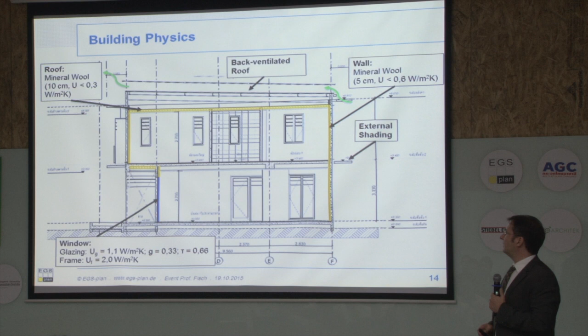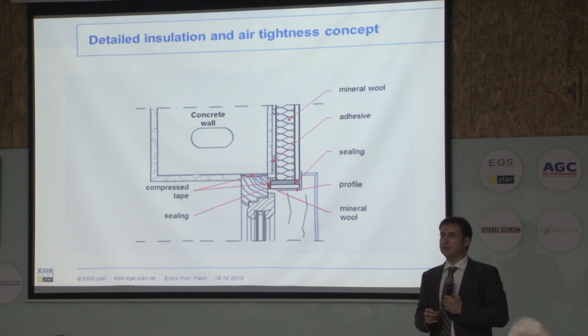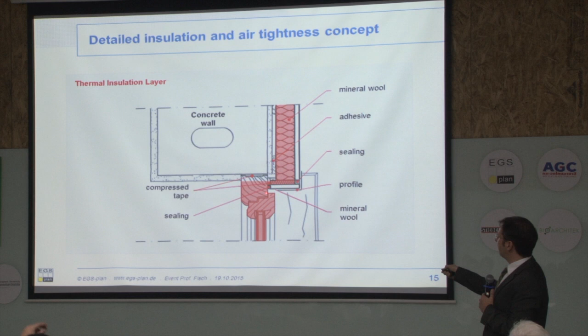We have external shading, not only in the area of the window, but the shading also protects the wall to reduce the solar heat gains through the wall. Also the roof is back ventilated, which also reduces the cooling load in the building. So we are not only designing the rough overall building envelope, we also really go into detail, because in most projects where people are applying thermal insulation, they probably put the insulation until here, and then you have a gap between the window frame and the thermal insulation, and through this gap you are losing a lot of thermal energy. So what we are doing in our project is we are trying to cover the window frame as far as possible with thermal insulation to reduce this thermal bridge.